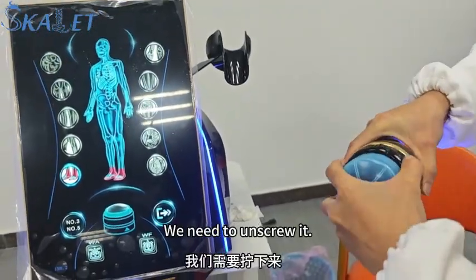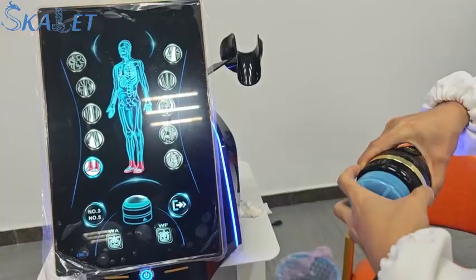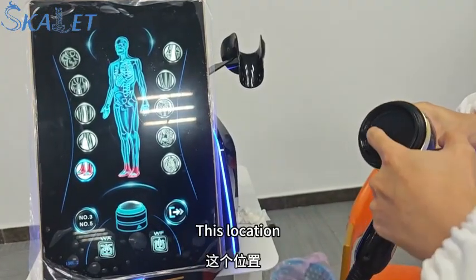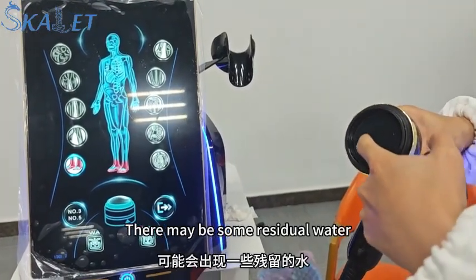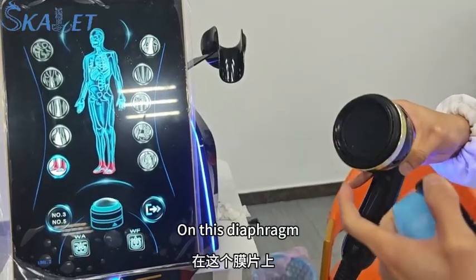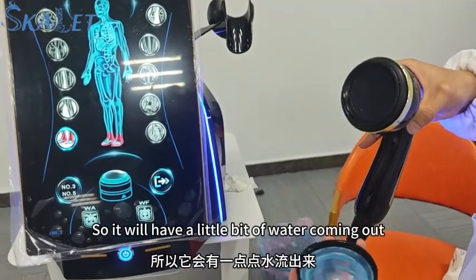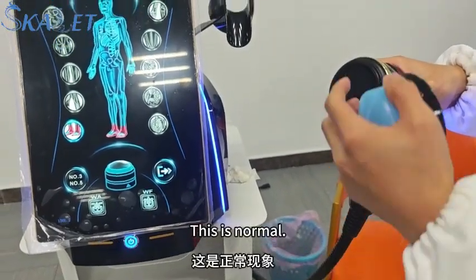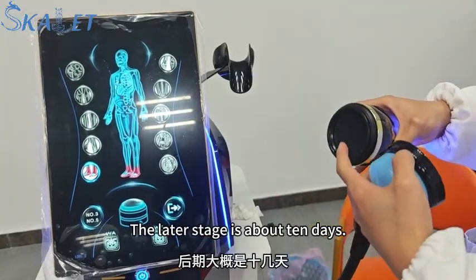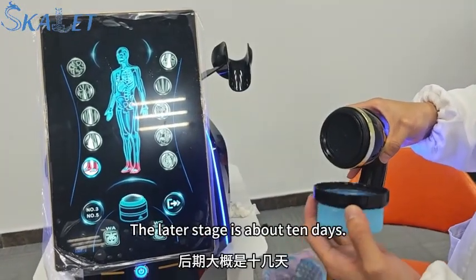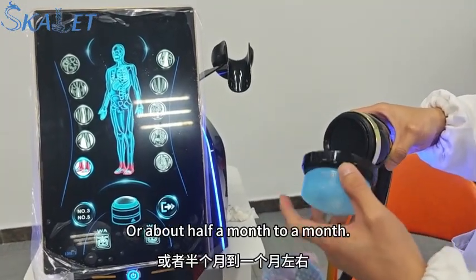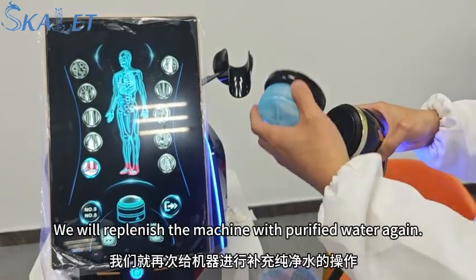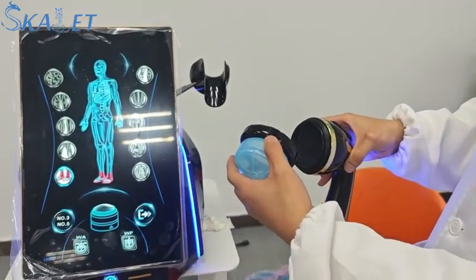We need to unscrew it. After unscrewing this location, there may be some residual water on this diaphragm, so it will have a little bit of water coming out. This is normal. The later stage is about 10 days, or about half a month to a month. We will replenish the machine with purified water again.